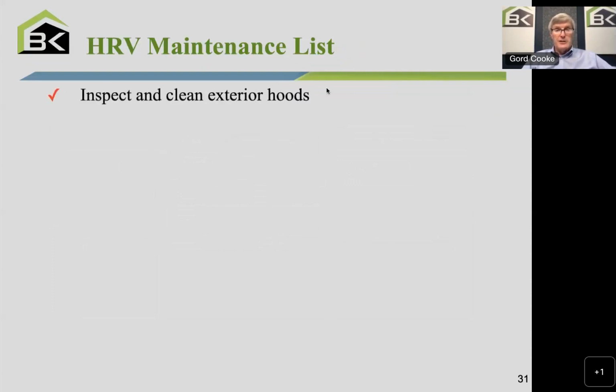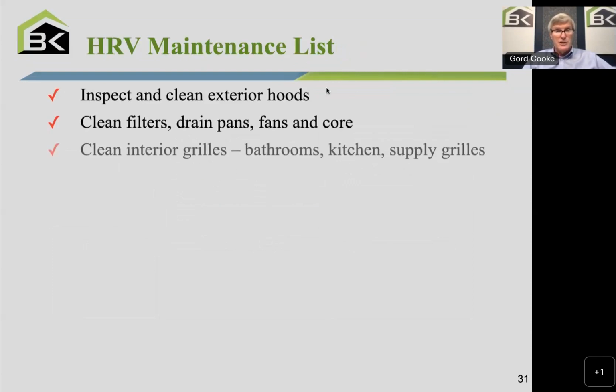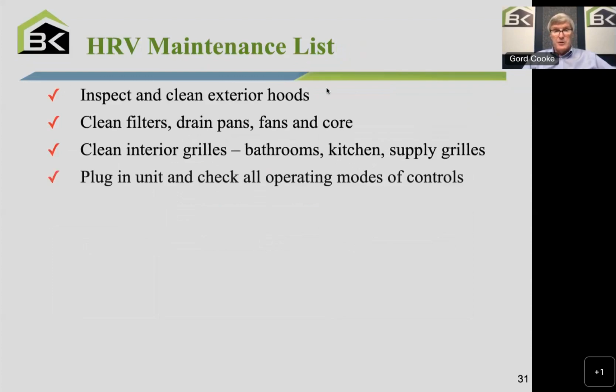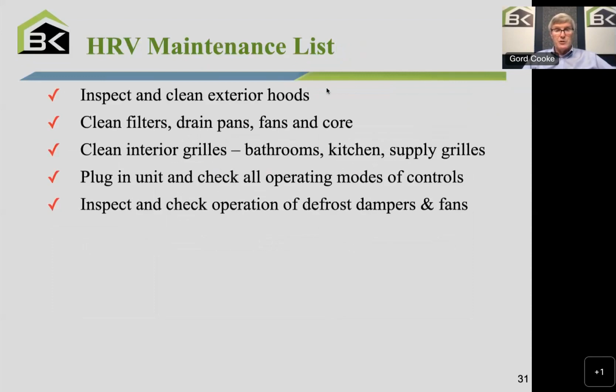We're going to inspect and clean those exterior hoods. We're going to clean the filters, the drain pans, the fans, and the core. We're going to clean the interior grills. We're going to plug the unit back in. We're going to check all the operating modes of control. We're going to inspect and check operation of the defrost dampers and fans.